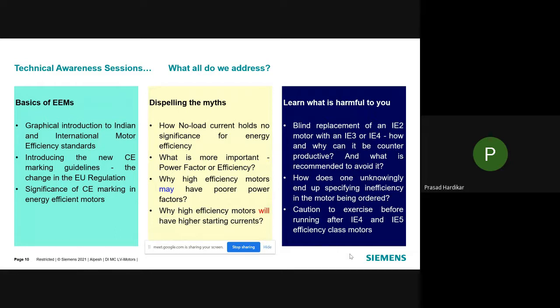So we discuss every aspect of such consultant specifications and clauses that cause oversizing of motors and thereby inefficient operation. You do go for an IE4 motor, but because you have restricted certain requirements like starting current, the motor does not perform. I will back this up with a proper IEC document showing that if you restrict starting currents, you may not get efficiencies higher than IE3.